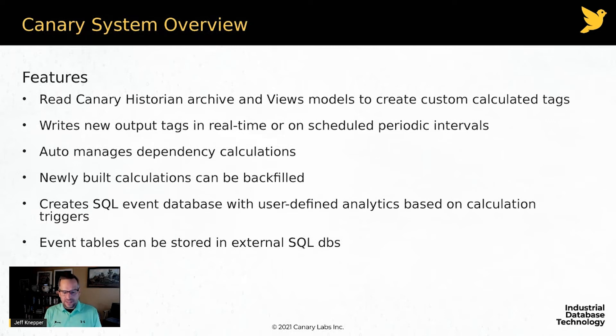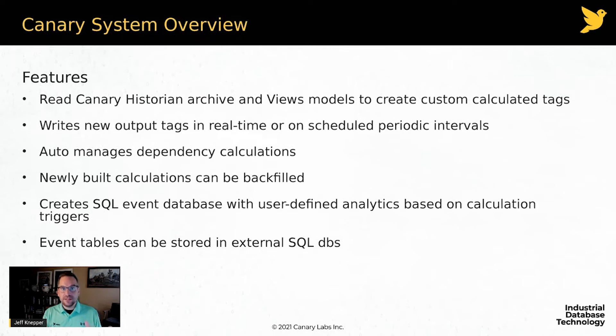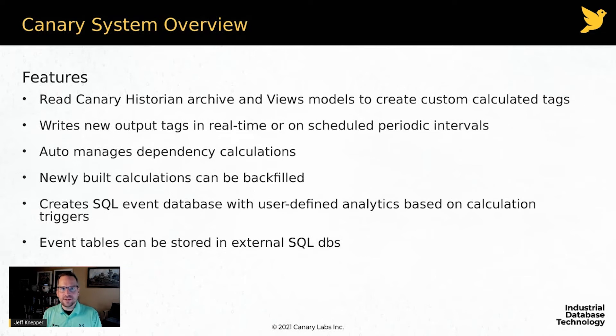Imagine you're in your sandbox working with the calc server, trying to create the perfect expression to generate a new piece of information — but how do you validate that without waiting a week to check results? We've given you the ability to backfill calculations. You can work on your expressions, backfill immediately, look at the data, validate the results, and if you're happy, deploy that calculation. If not, you can make changes and overwrite the backfilled values with new ones.